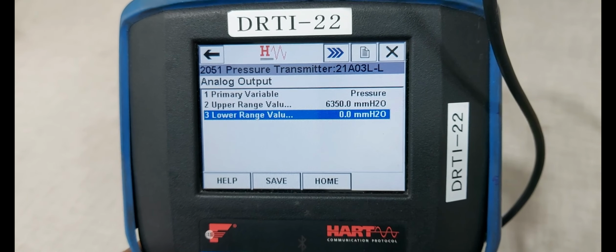Next we are changing the upper range value. Actually upper range value as per the data sheet is 900 mm H2O. Enter, send it, then OK, then OK. Now output value also changed to 4.139 milliamps DC. Next select the home menu.